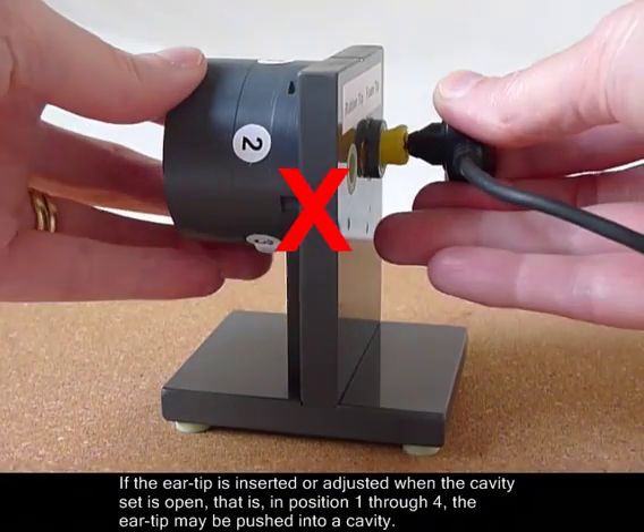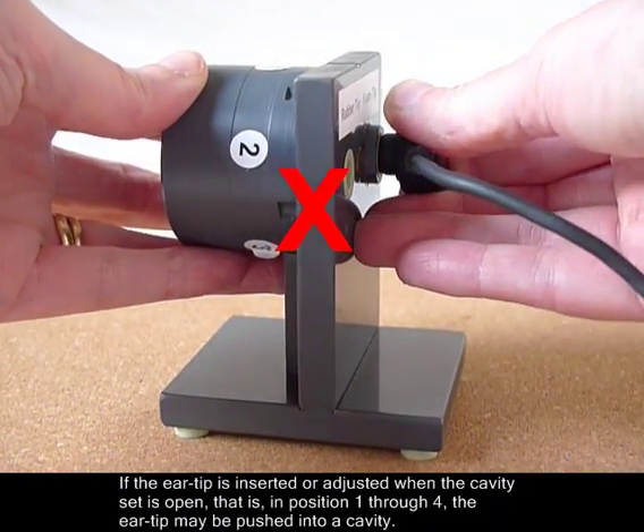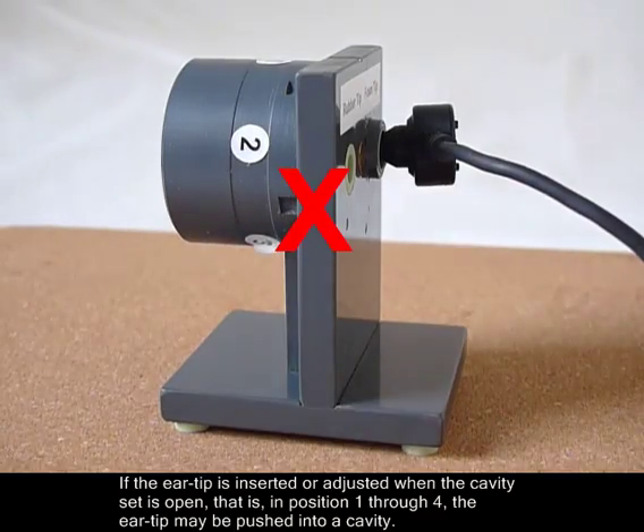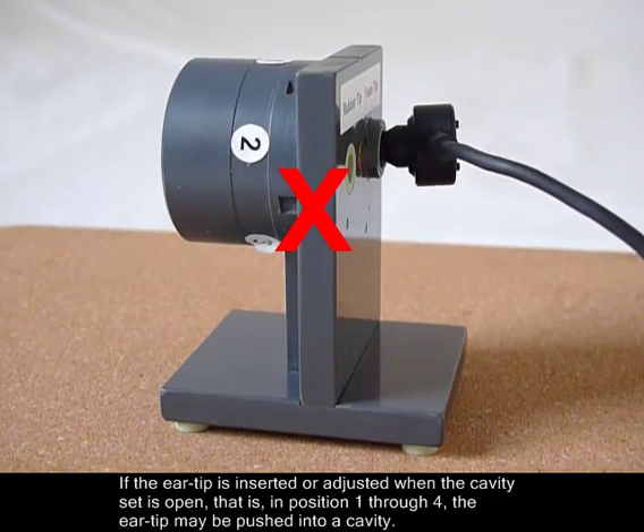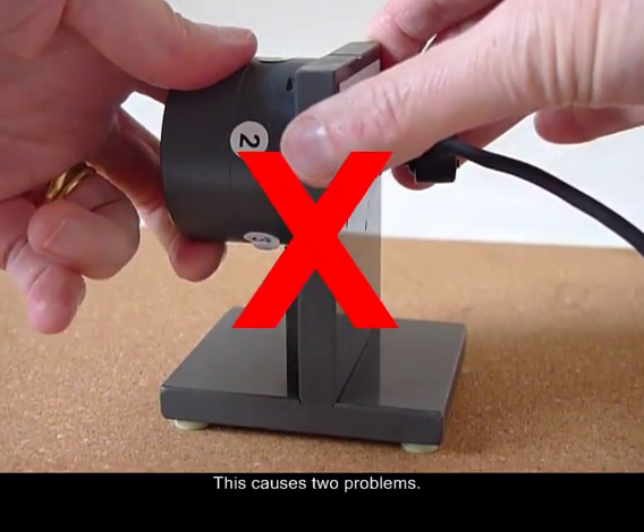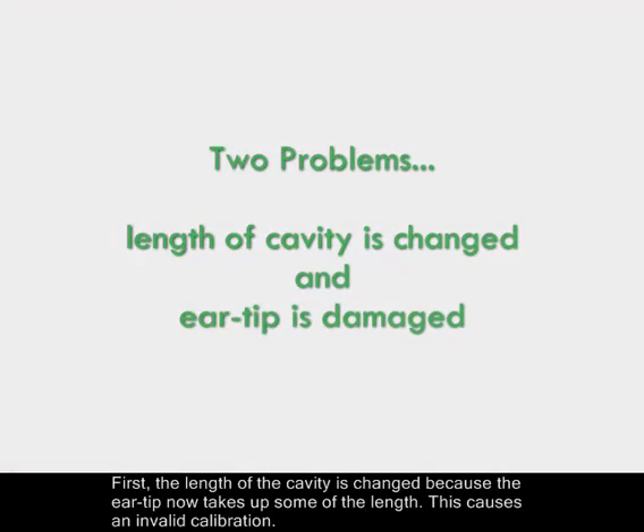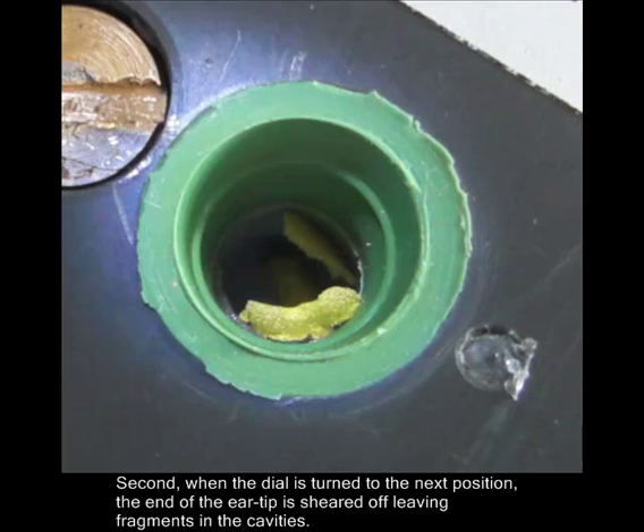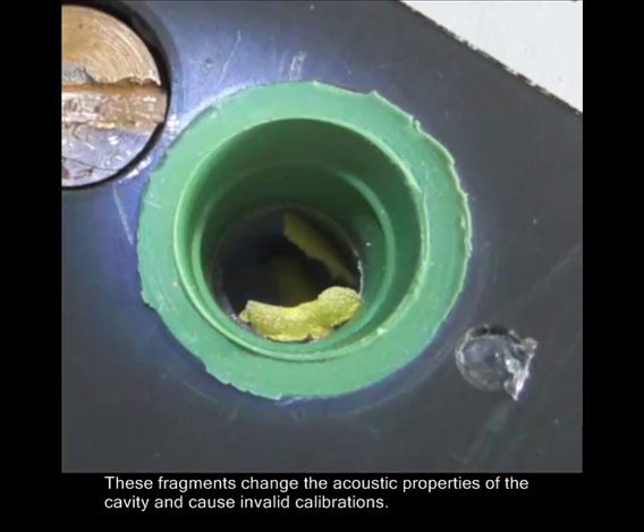If the ear tip is inserted or adjusted when the cavity set is open, that is, in position 1 through 4, the ear tip may be pushed into a cavity. This causes 2 problems. First, the length of the cavity is changed because the ear tip now takes up some of the length. This causes an invalid calibration. Second, when the dial is turned to the next position, the end of the ear tip is sheared off, leaving fragments in the cavities. These fragments change the acoustic properties of the cavity and cause invalid calibrations.